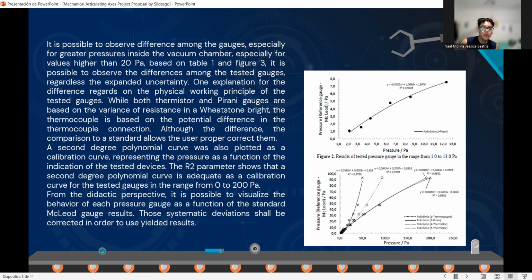One explanation regards the physical working principle of the tested gauges. While both thermistor and Pirani gauges are based on balance of resistance in a Wheatstone bridge, the thermocouple is based on the potential difference in the thermocouple connection. Despite the difference, the comparison to a standard allows the user to properly correct them.